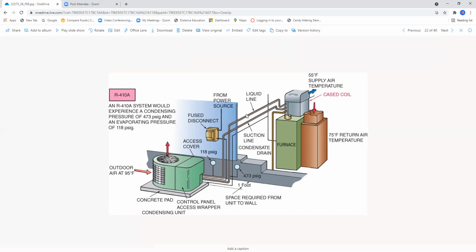Then of course you have your liquid line, suction line, you have your upflow furnace, you have your cased coil on top, your ductwork above that, and we're going in the supply ducting at 55 degrees. We're coming back in return air about 75. So 75, 55, that's a 20-degree split, which is ideal. And then of course it's the return air, and hopefully you have a filter installed to trap all the dirt.